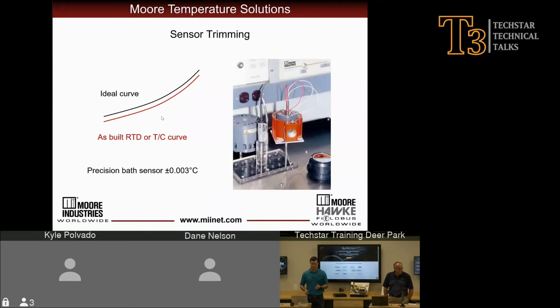At Moore Industries, we use a precision bath calibration for our sensors. So effectively, we take the temperature sensor and put it in a hot oil bath at one precise temperature that's within plus or minus 0.003 degrees Celsius. And then we calibrate a transmitter and that sensor to that defined temperature in the bath. We then take another operating temperature that our customer might provide us and calibrate at that temperature. So we have two defined temperatures that we're calibrating the sensor at.